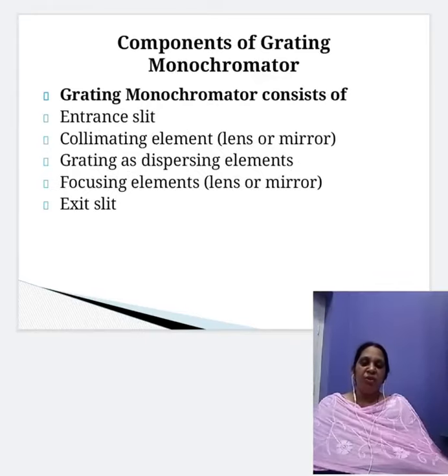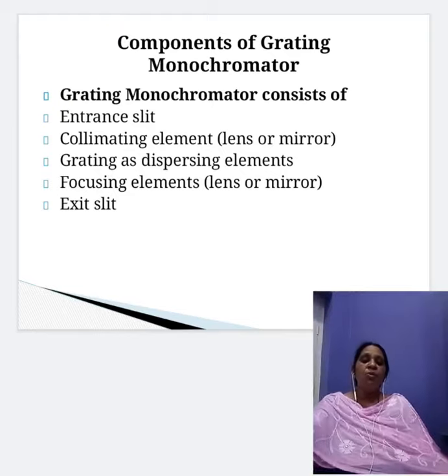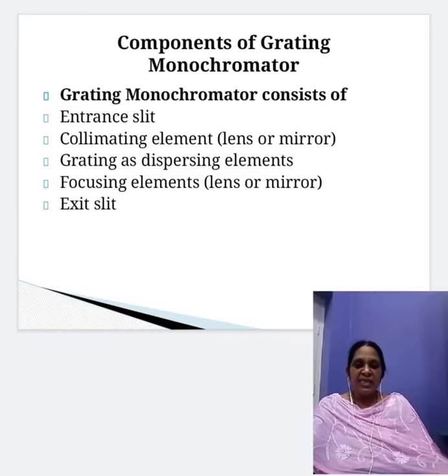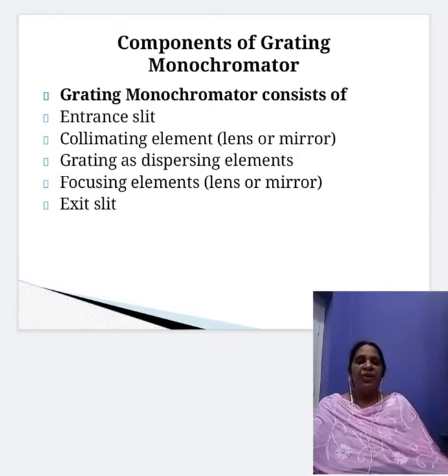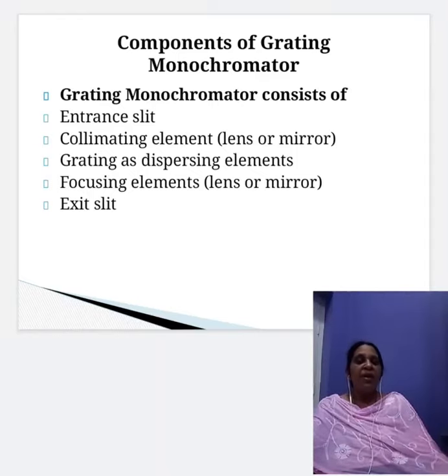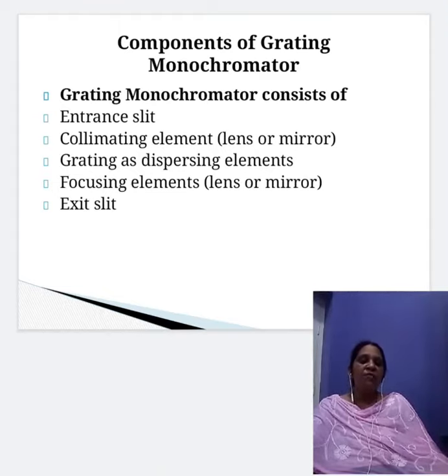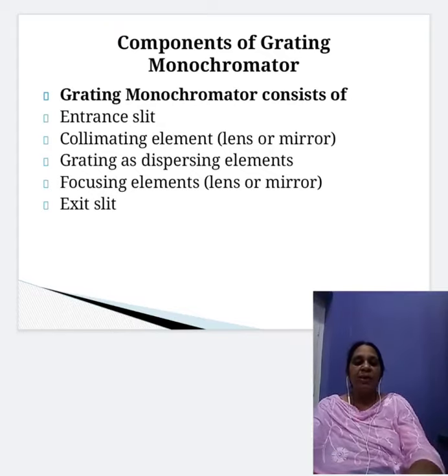The grating monochromator consists of: an entrance slit that provides a narrow optical image of the radiation source; a collimating element that makes the light rendered parallel from the entrance slit; a grating used for dispersing the incident radiation; a focusing element that reforms the images of the desired spectral band; and an exit slit used to isolate the desired spectral band.